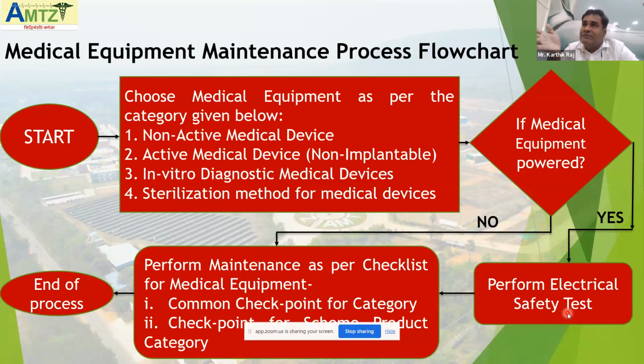Once the equipment is accepted, you are using the equipment. You may be doing PPM, planned preventive maintenance, or you may do some servicing. If you're doing it, then you have to follow the IEC 62353 standard. It defines the basic requirements of the electrical safety testing. Now you may have a doubt about why it is IEC 62353.